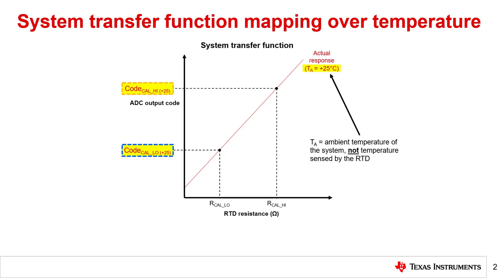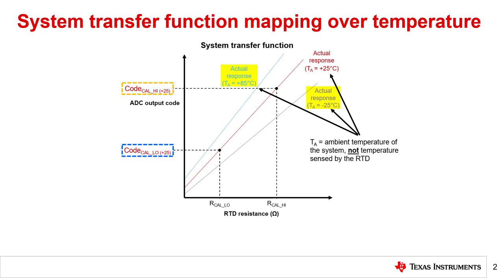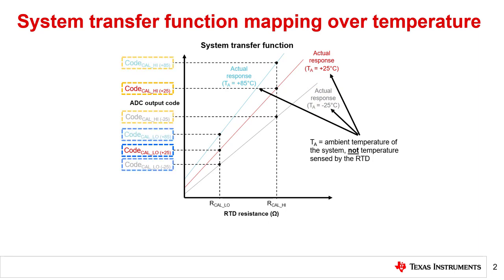However, as discussed in previous Precision Labs modules, the magnitude of each error source can change with temperature, which in turn changes the system transfer function. For example, hypothetical transfer functions at negative 25 degrees Celsius and 85 degrees Celsius are shown in gray and light blue respectively. Since the transfer function is changing across ambient temperature, the code range corresponding to the RTD curve can change as well. Possible code ranges are shown on the left for transfer functions in gray and light blue. These represent additional system error introduced by the change in temperature.